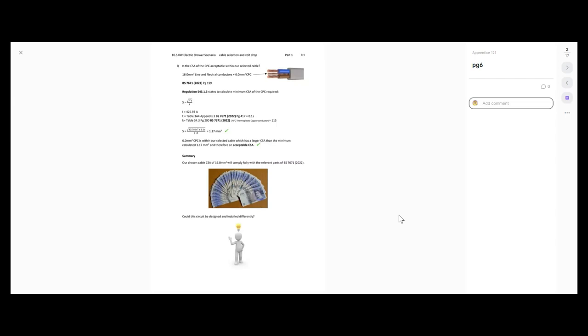In summary, our chosen cable of 16mm squared will comply fully with all the relevant parts of BS 7671. But there is something to think about for everyone who's listened: is there a way that the circuit could be designed and maybe installed differently? Would that affect the size of cable and ultimately the cost and ease of installation? Because 16mm — the cost of the cable is going to be quite expensive, running that through the fabric of the building. Even the best pull switches like the Crabtree 50 amp one are difficult to connect, and in the shower it's quite difficult to do.